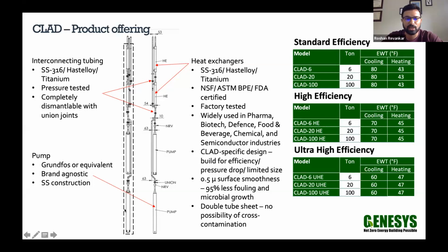Now, this is how the CLAD unit actually looks, and this is the diagram. It is made of SS316 stainless steel. The finish on the heat exchanger is really, really smooth. It's 0.5 microns smoothness. The reason that was picked was to avoid any growth or fouling.